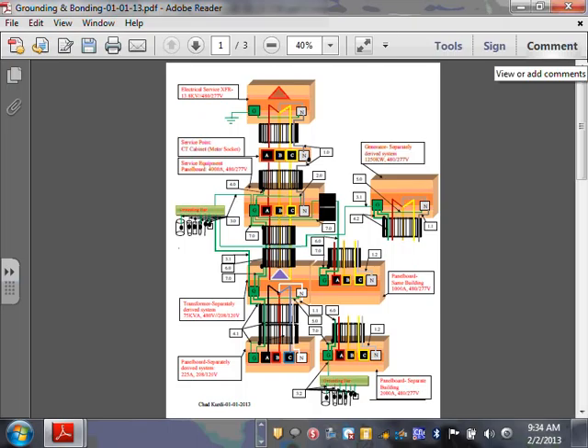If it's a delta, I've never... Do you guys have a delta service to a building? Anybody have seen a delta service to a building? A delta to a building? Typically, did you guys? Our older buildings had that. Yeah. Okay. Is it center tap though? No, it was a corner grounded system. Okay. How did you get your 120 then? Well, they had transformers all over, but yeah, the incoming was the delta. Delta corner grounded, part of the system. Okay. So typically, guys, good point.